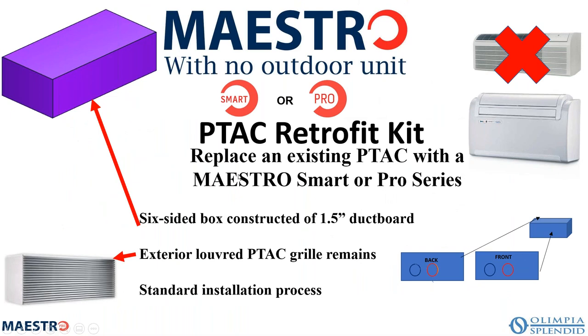This is something we're quite proud of, is we're just ready to release our retrofit kit. There are an awful lot of PTACs installed throughout the country. And many of them are reaching that 15 to 20 year range, which means it's time to replace them. But a lot of people don't like those loud, clunky PTACs that are noisy and they're just not attractive. So you can take the existing PTAC and you pull it out of its sleeve, okay?